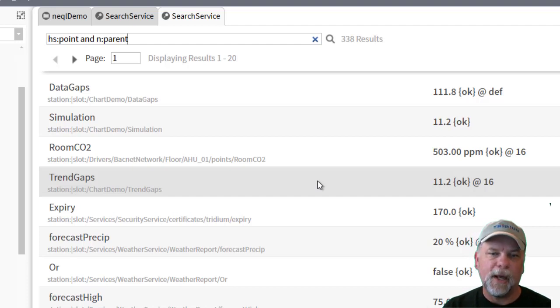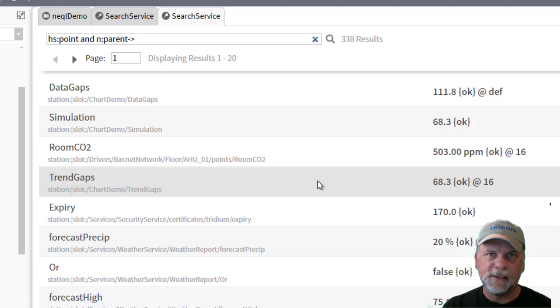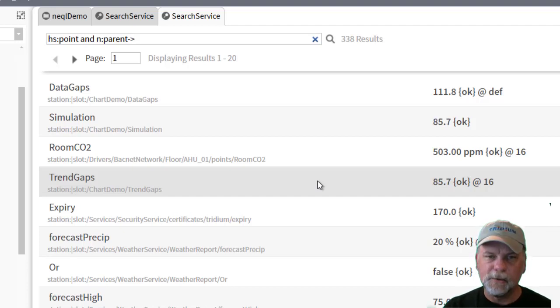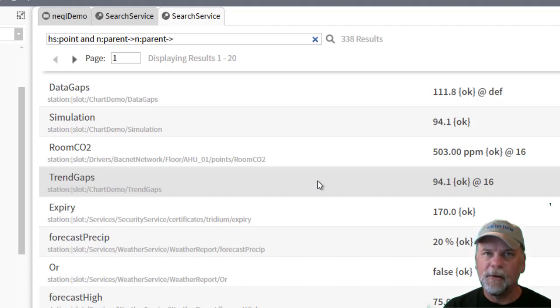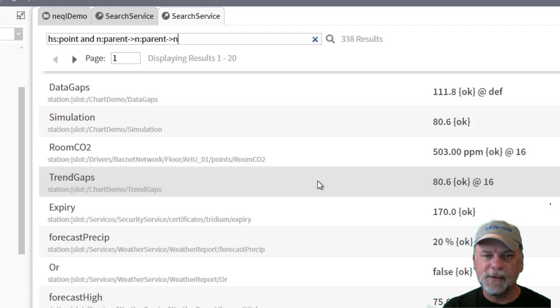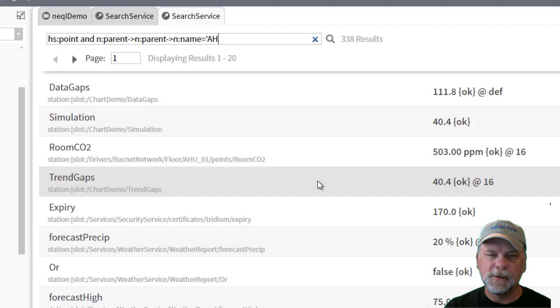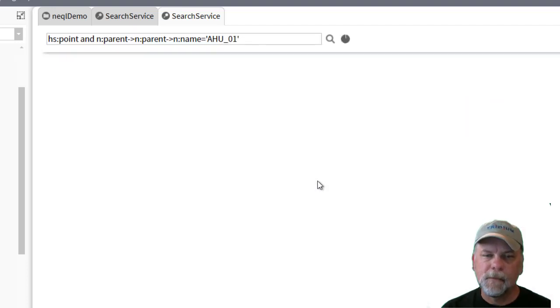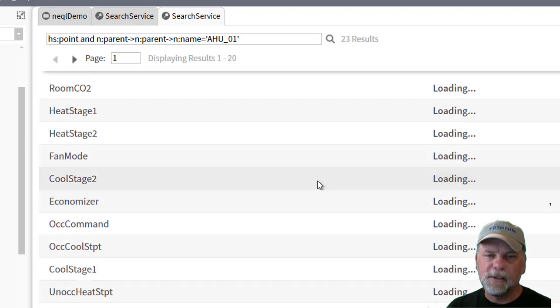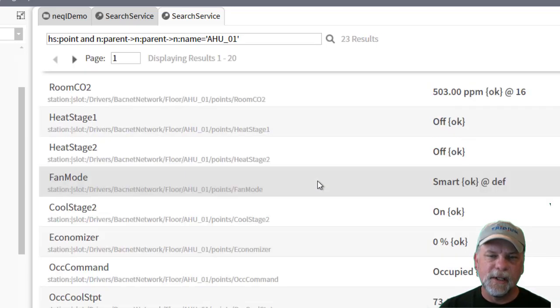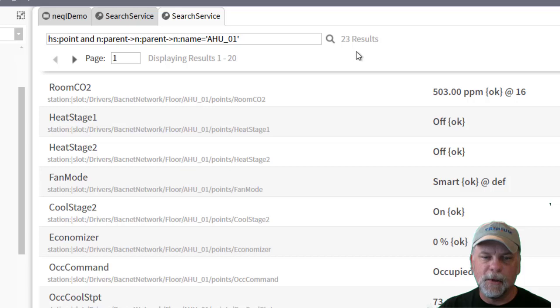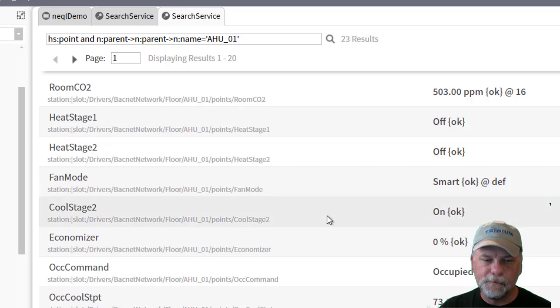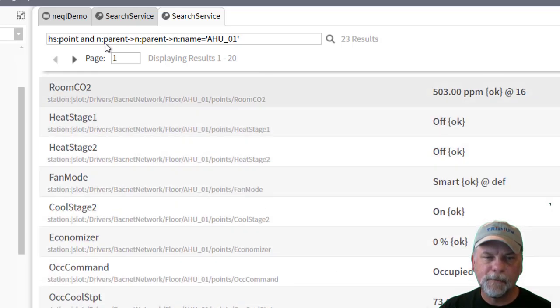If it's outbound from the point it will be dash and greater than. If it was inbound it would be less than and dash, and I'll show you the reciprocal relation here in a second. n colon parent again from the points container outbound, that should get me to the device, and then I could check the n colon name tag equals AHU underscore 01. This should find just the control points that are associated with air handler one. So now my results are much more limited just to air handler one.